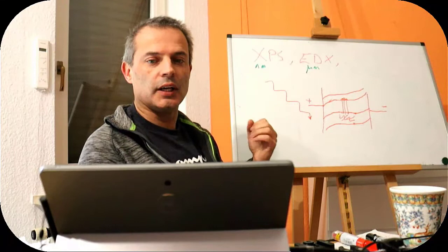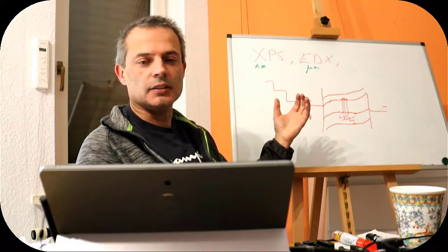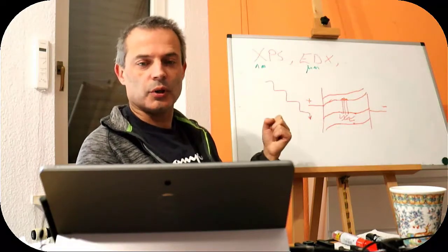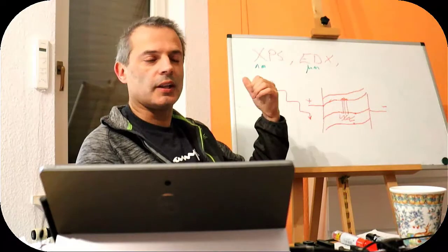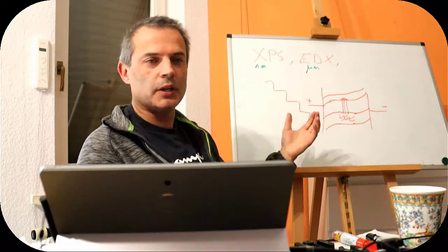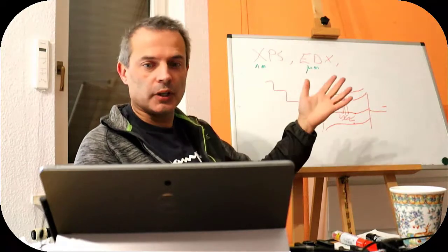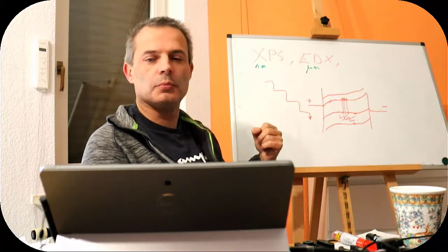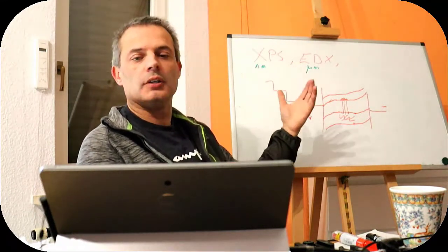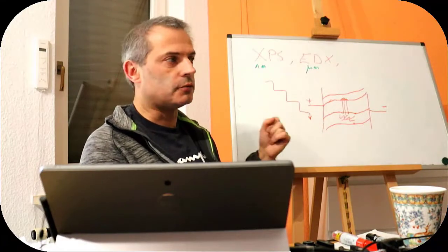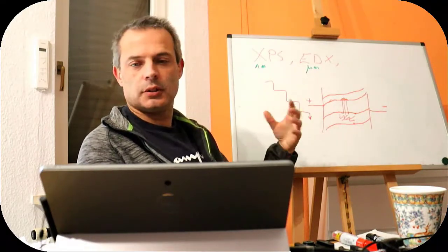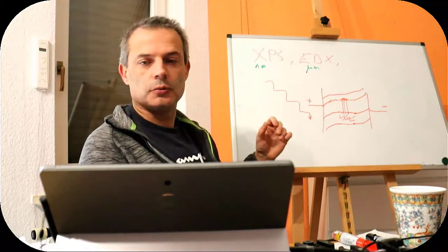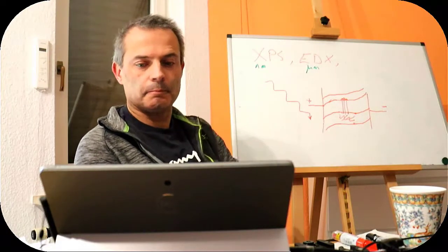Because we're counting individual electrons and individual photons, obviously it is a time-consuming technique because the reliability of the process is low. We count one photon, that means we've got one piece of information, and as you saw, the peaks are smooth curves, so we need to measure a lot of those to be able to build a curve, which means that very often you're waiting for some minutes, 10 minutes possibly. Sometimes if you want a good 2D image at reasonably high resolution, it can be hours, but typically it's minutes to get a good spectrum to be able to tell what is in there.